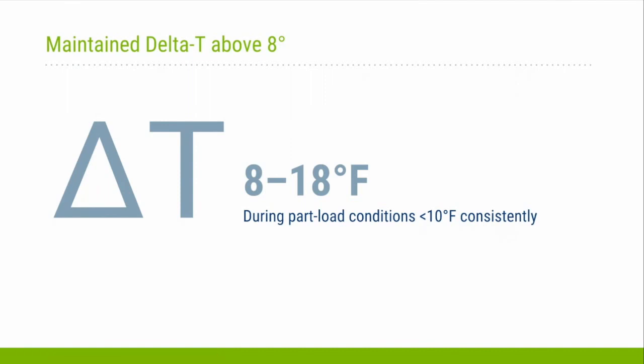Typically, constant volume systems in a primary, secondary chill water plant design struggle with low delta T during low load, and even sometimes during greater load. So this was a significant improvement, and it resulted in operational improvements as well. During low loads, as we noted in March, April, wintertime, the operation staff encountered a lot of times when the chillers would cycle off on low loads or other anomalies related to low delta T. Let's go to the next slide, please.